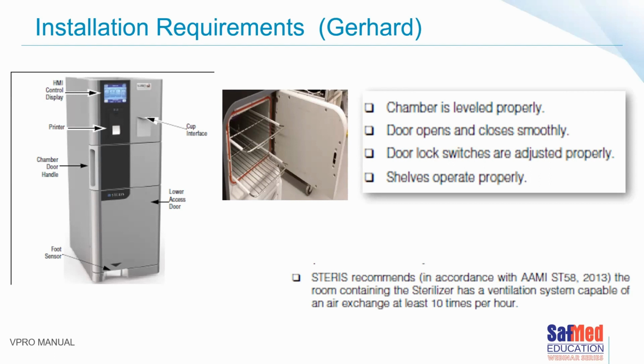Okay, for this specific machine, the installation requirements will still depend on the make and the model of the device. But with the VHP sterilizer, there's no need for any water or drainage. The only utility that the hospital needs to supply for this machine is three-phase electricity in the case of the big machine, and single phase for the smaller machine. So from a hospital point of view, it's a very easy installation.